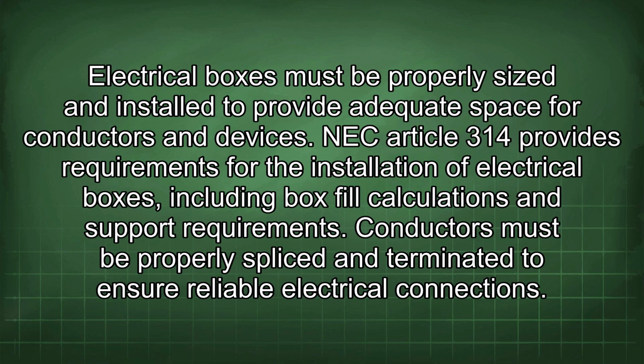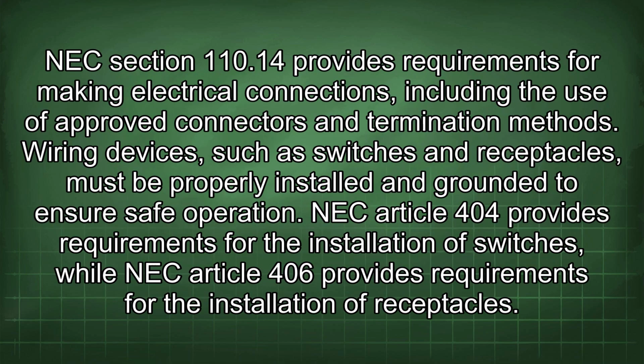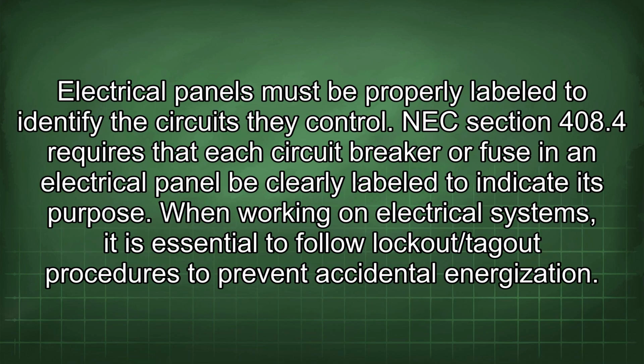Conductors must be properly spliced and terminated to ensure reliable electrical connections. NEC Section 110.14 provides requirements for making electrical connections, including the use of approved connectors and termination methods. Wiring devices, such as switches and receptacles, must be properly installed and grounded to ensure safe operation. NEC Article 404 provides requirements for the installation of switches, while NEC Article 406 provides requirements for the installation of receptacles. Electrical panels must be properly labeled to identify the circuits they control. NEC Section 408.4 requires that each circuit breaker or fuse in an electrical panel be clearly labeled to indicate its purpose.